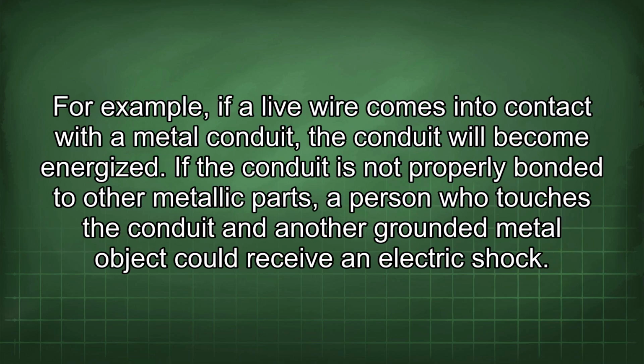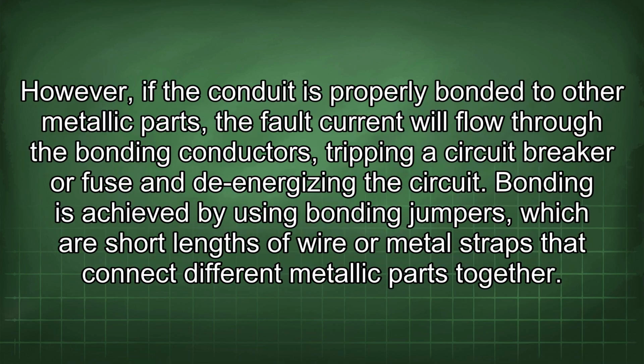For example, if a live wire comes into contact with a metal conduit, the conduit will become energized. If the conduit is not properly bonded to other metallic parts, a person who touches the conduit and another grounded metal object could receive an electric shock. However, if the conduit is properly bonded to other metallic parts, the fault current will flow through the bonding conductors, tripping a circuit breaker or fuse and de-energizing the circuit.